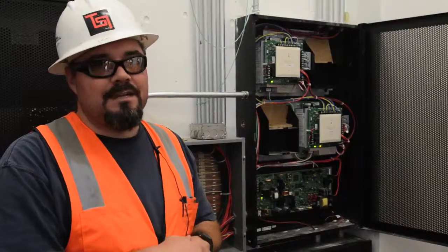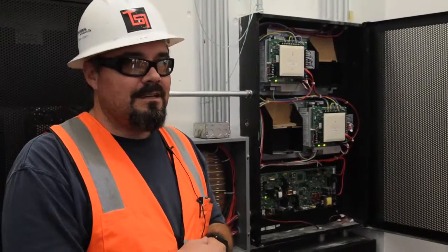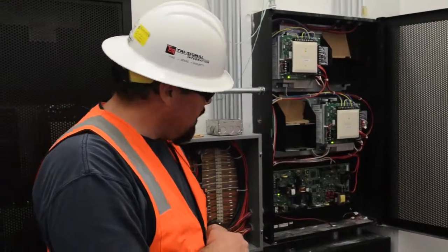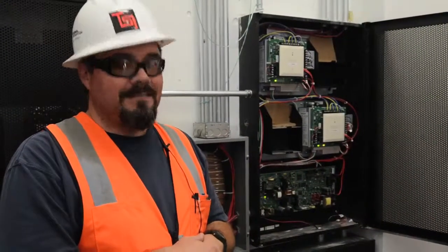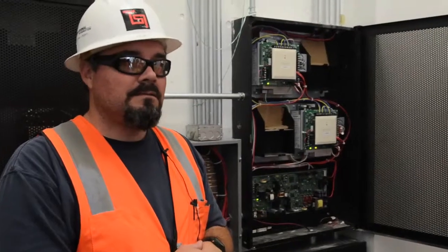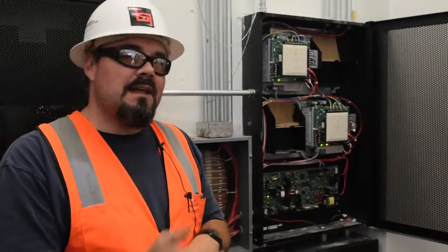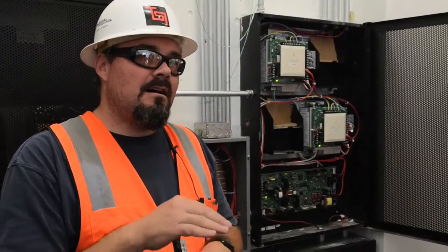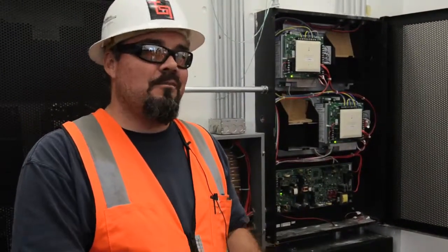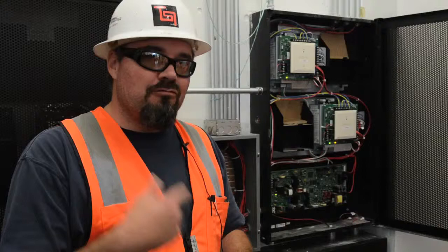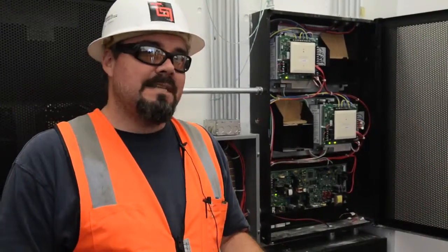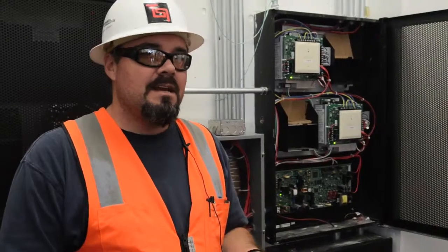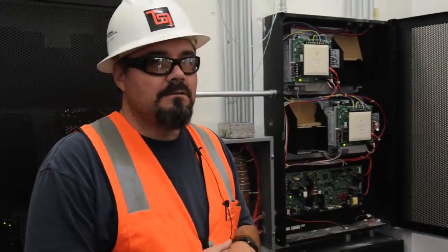It's one unit, and they're all System Sensor devices. And I believe that's what you have over at Division 9. I did that job a few years ago. I just never really heard an alarm, so I always hear the whoop. I thought that was part of the strobe, but it's not. It's audible in the strobe, but that's just a plain horn strobe. This is a speaker strobe, a little bit more advanced, where it has the message and that whoop you hear here. That's called the California whoop. You didn't have to have the message, but MTA requires a message in English and Spanish, so we put that in for you. Okay, so then these strobes are capable of voice.